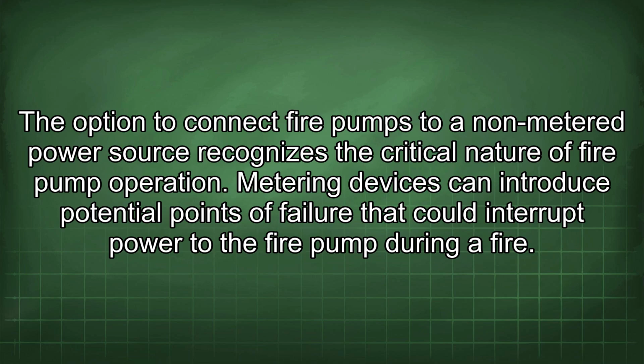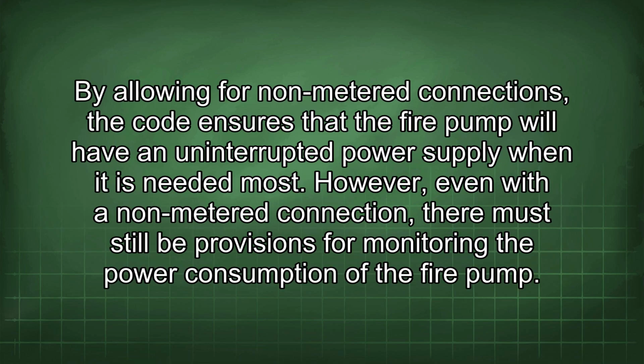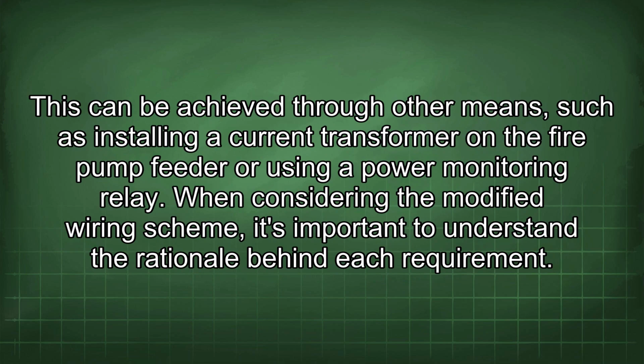The option to connect fire pumps to a non-metered power source recognizes the critical nature of fire pump operation. Metering devices can introduce potential points of failure that could interrupt power to the fire pump during a fire. By allowing for non-metered connections, the code ensures that the fire pump will have an uninterrupted power supply when it is needed most. However, even with a non-metered connection, there must still be provisions for monitoring the power consumption of the fire pump. This can be achieved through other means, such as installing a current transformer on the fire pump feeder or using a power monitoring relay.